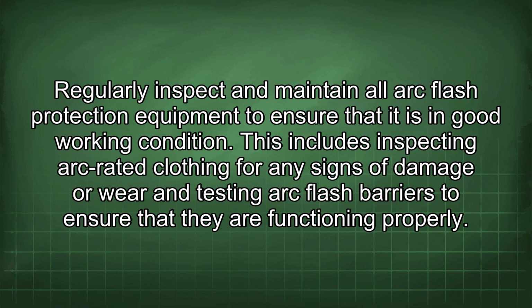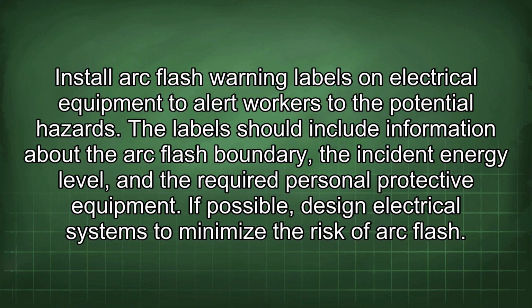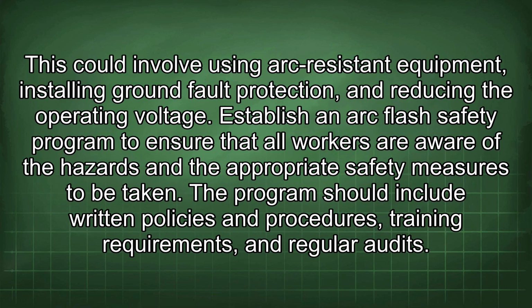Install arc flash warning labels on electrical equipment to alert workers to the potential hazards. The label should include information about the arc flash boundary, the incident energy level, and the required personal protective equipment. If possible, design electrical systems to minimize the risk of arc flash. This could involve using arc-resistant equipment, installing ground fault protection, and reducing the operating voltage. Establish an arc flash safety program to ensure that all workers are aware of the hazards and the appropriate safety measures to be taken. The program should include written policies and procedures, training requirements, and regular audits.